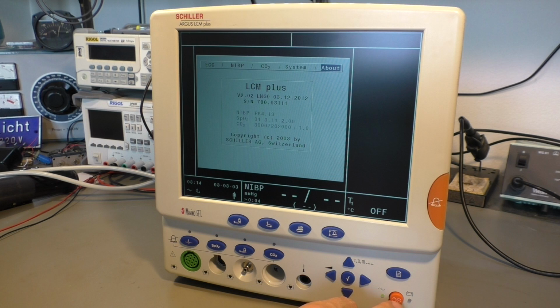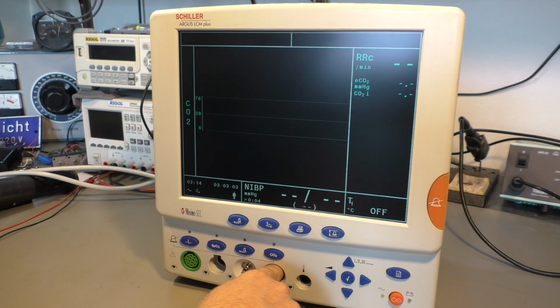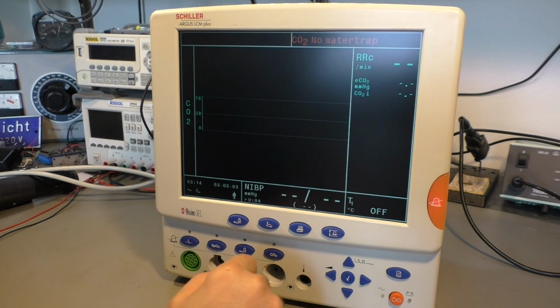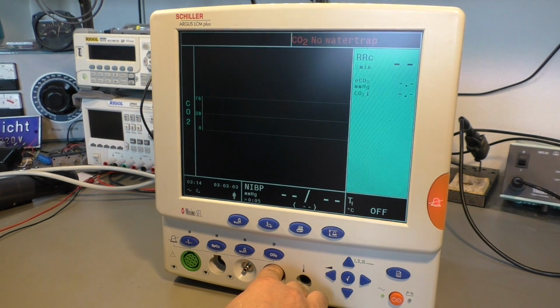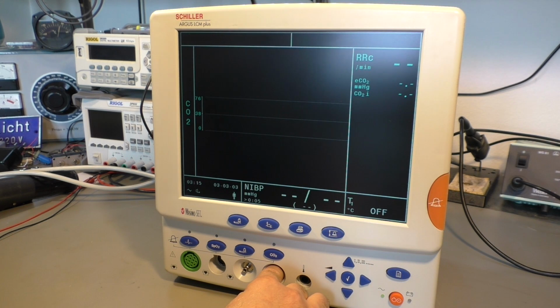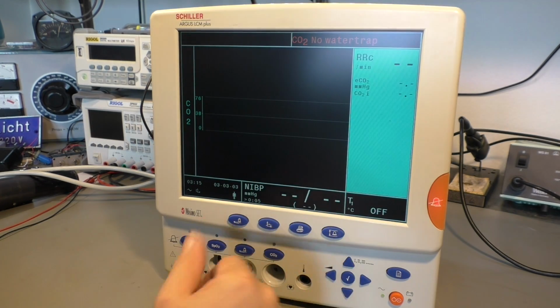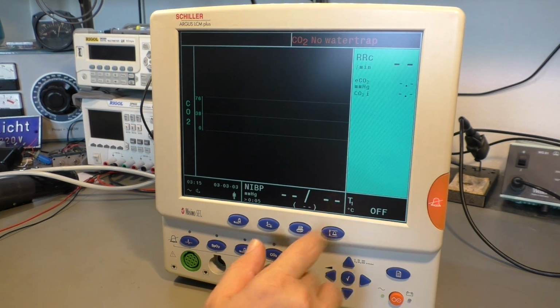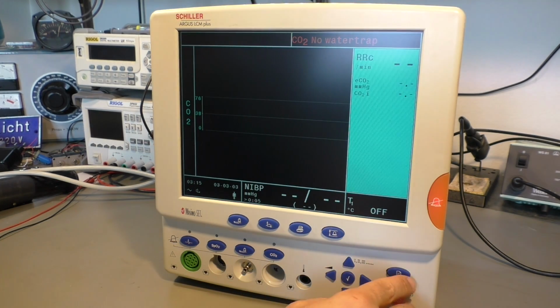The unit also has a battery, but it seems it doesn't work. The only thing I get to work is this CO2 measurement. Now a pump starts sucking in through that port. There is a little micro switch that detects if the so-called water trap is installed. That's a filter that holds back any moisture, because the unit here doesn't like any water in the system. And if that micro switch is pushed, the pump starts pumping. Of course, it doesn't display anything here because it's not measuring anything. Maybe that's also something that doesn't work. I don't know how it works.